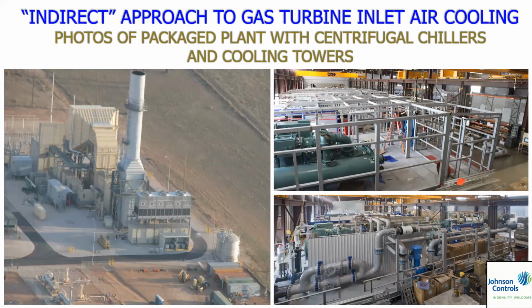All right, we talked about fin fan coolers when you don't have makeup water available. When you do have makeup water available, and you can go with a traditional cooling tower, then we can put packages together. You've heard of modules. So we do modular construction where we build a chiller, put it in a box. Everything's there, pre-piped, put in a module, put in a house. Above this house, we got 3 cooling towers up above. So this is one, and then the turbine air house is right here in the back. So this is a completely modular system, put in a building below its cooling towers. So that's another approach we use.